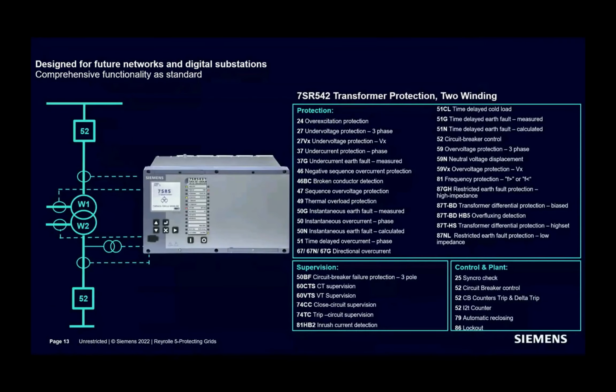Now, let's switch to 7SR5 which is our transformer protection relay. We examine it in two main variants, 2 winding and 3 winding. So we are just looking at the 2 winding solution now. The device provides differential protection for reactors and motors as well. Of course, it is mainly used for transformer protection.